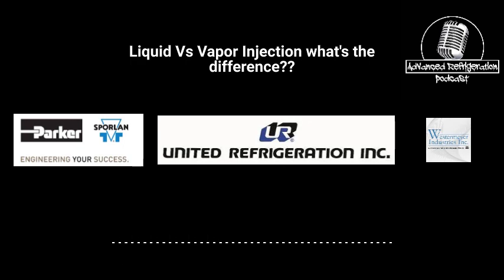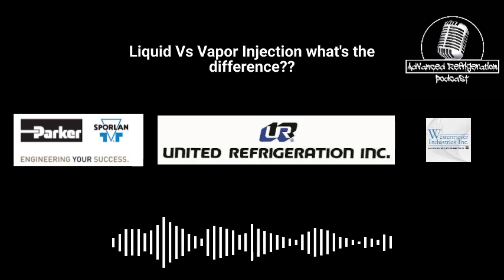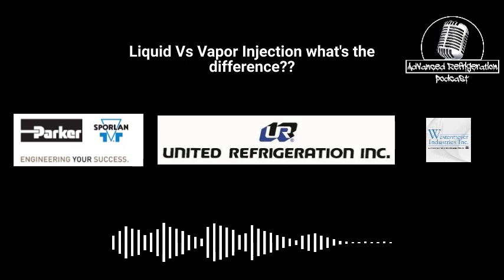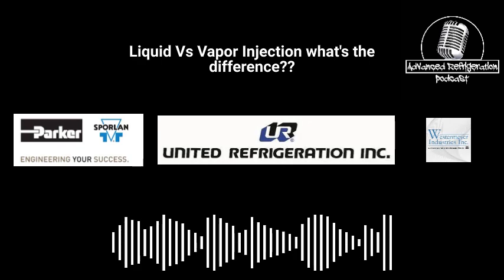On a regular mechanical expansion valve, that's perfectly fine. But if you are not telling that controller, typically a Sporlan superheat controller, that you're physically shutting off the liquid line solenoid, by applying the jumper to, I think it's terminals 27 and 28 on that superheat controller, which puts the electronic expansion valve in a pump down function. If you do not do that and you shut off the liquid line solenoid, what does it see? It sees an elevation in suction line temperature and a decrease in suction pressure, which gives you a high superheat. So instead of that valve clamping down because the system is now off, that valve is going to open up 100% because the superheat just keeps rising and rising.